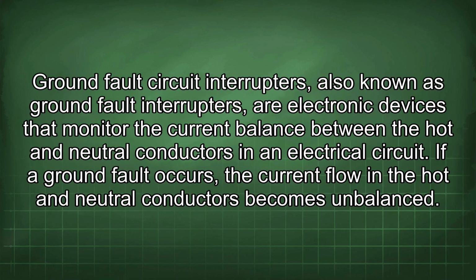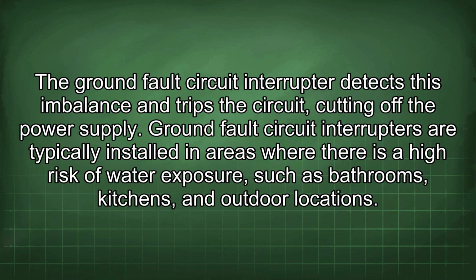Ground fault circuit interrupters, also known as ground fault interrupters, are electronic devices that monitor the current balance between the hot and neutral conductors in an electrical circuit. If a ground fault occurs, the current flow in the hot and neutral conductors becomes unbalanced. The ground fault circuit interrupter detects this imbalance and trips the circuit, cutting off the power supply. Ground fault circuit interrupters are typically installed in areas where there is a high risk of water exposure, such as bathrooms, kitchens, and outdoor locations.